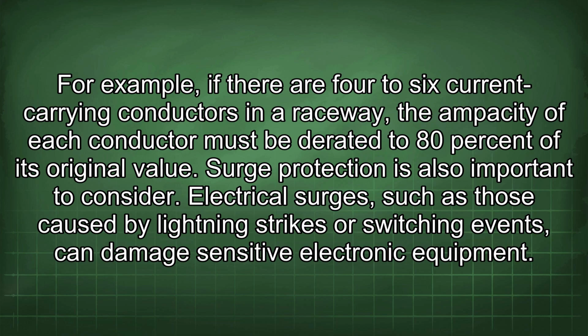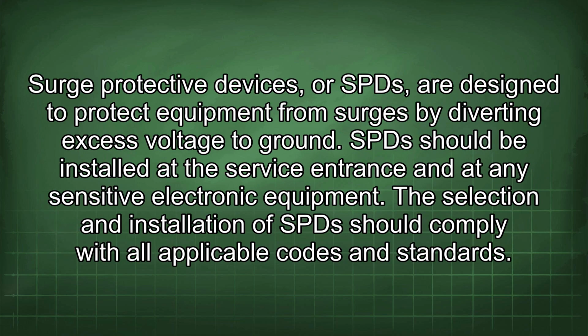Surge protection is also important to consider. Electrical surges, such as those caused by lightning strikes or switching events, can damage sensitive electronic equipment. Surge protective devices, or SPDs, are designed to protect equipment from surges by diverting excess voltage to ground. SPDs should be installed at the service entrance and at any sensitive electronic equipment. The selection and installation of SPDs should comply with all applicable codes and standards.